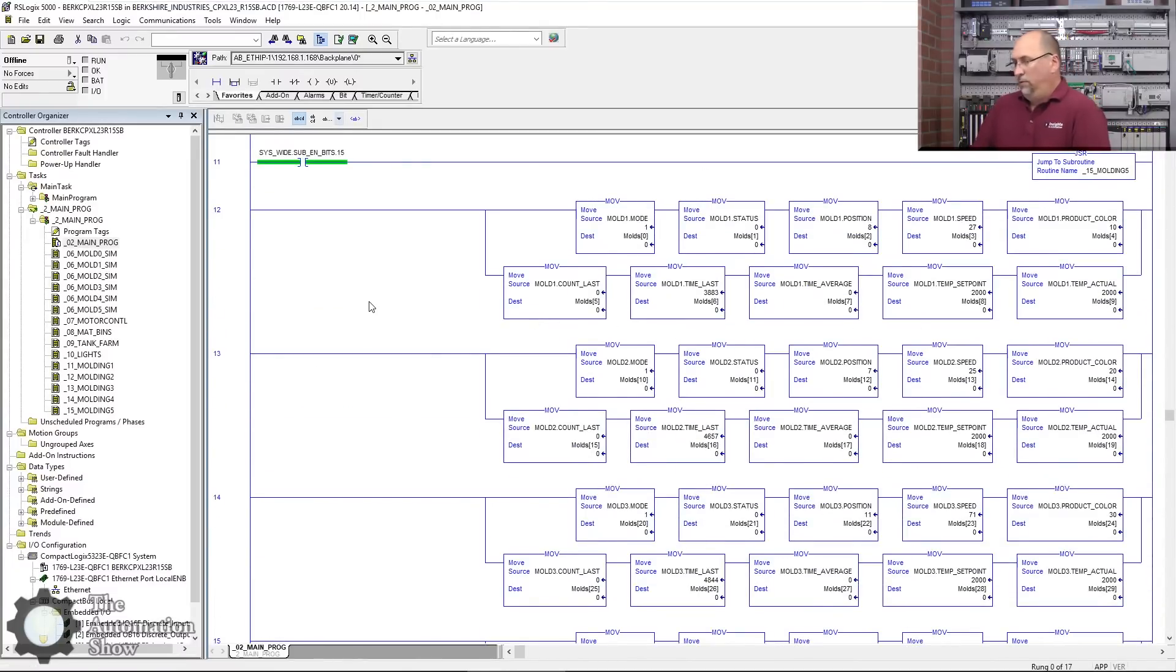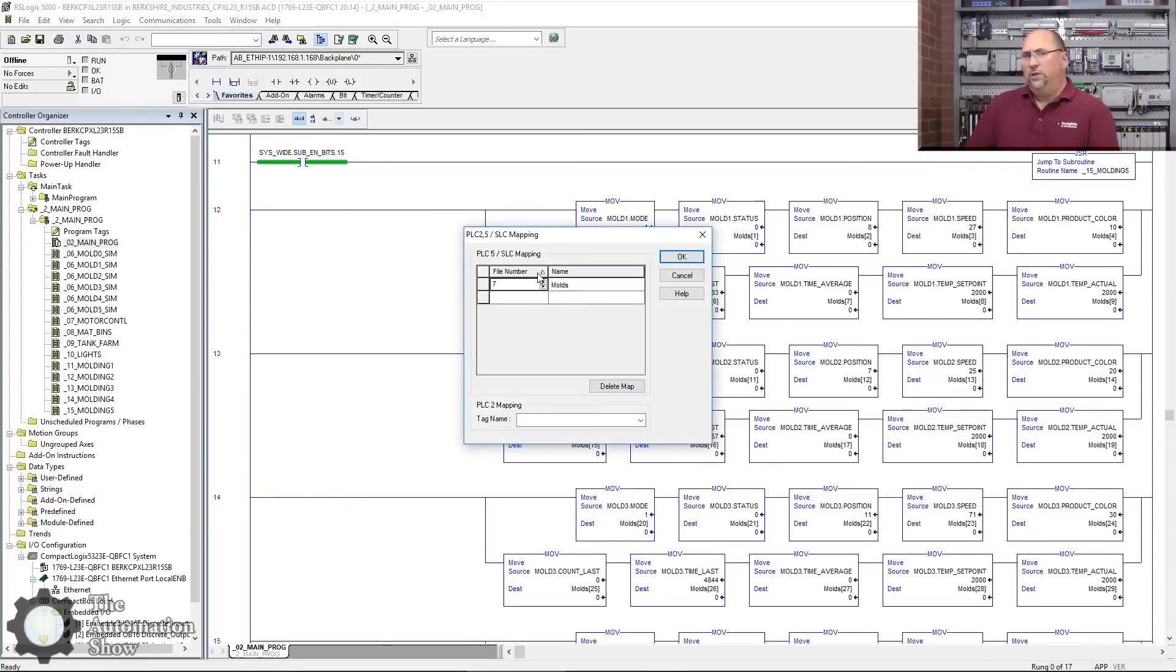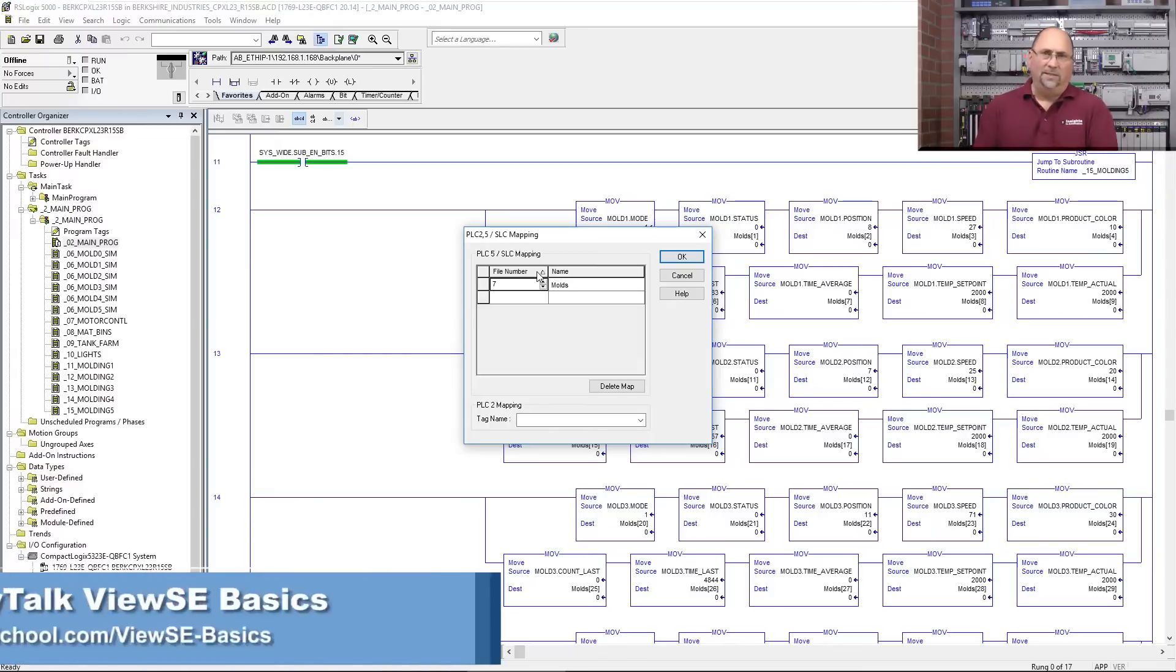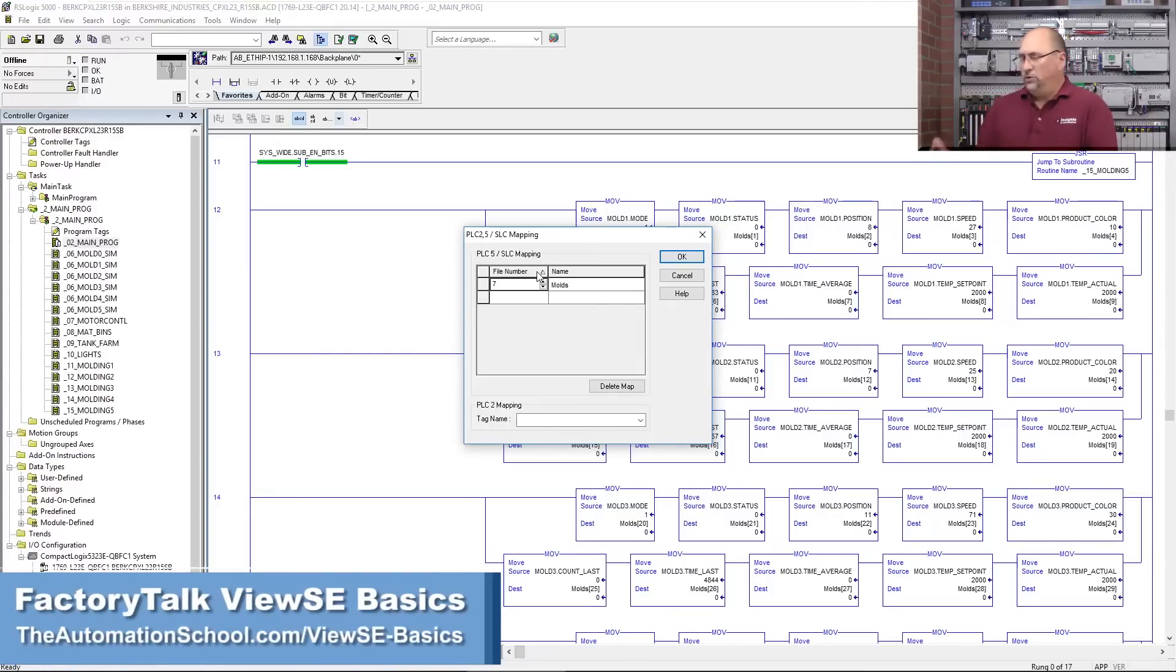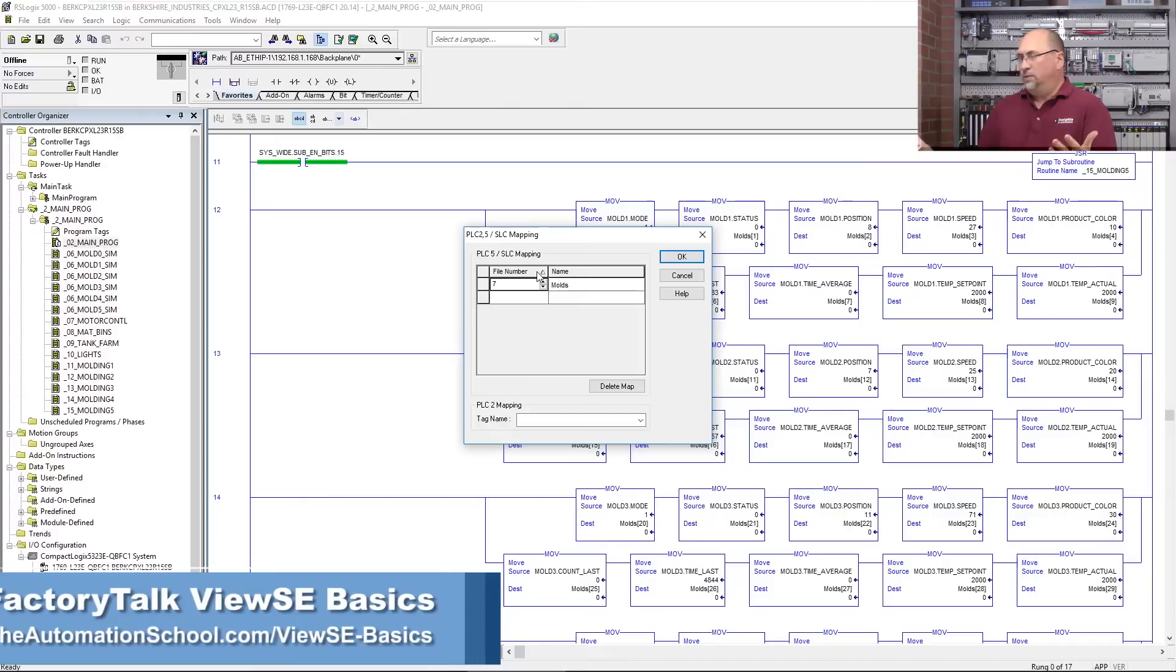So I have to put some code in here to move all the right data into the right words. So a lot of work if you want your ControlLogix to appear to be a SLC 500 or MicroLogix using that Map PLC/SLC Messages.